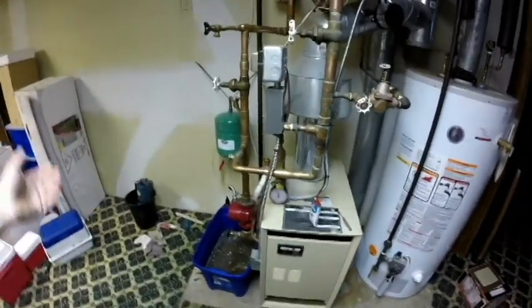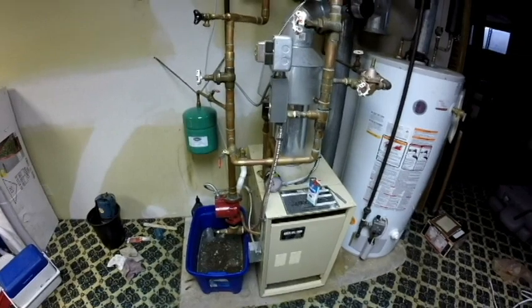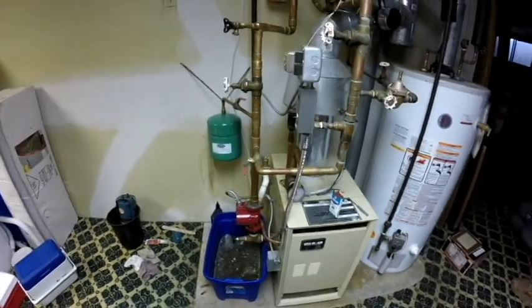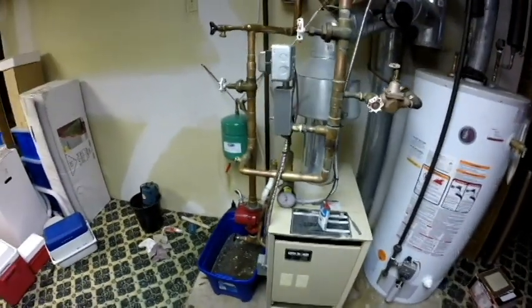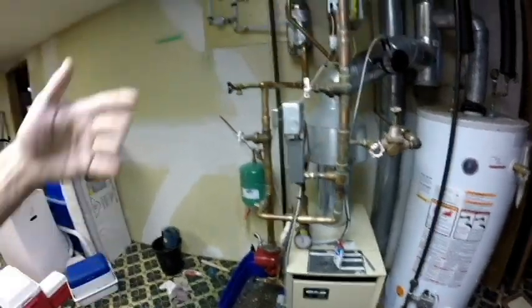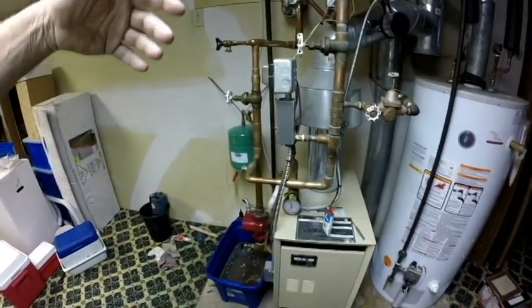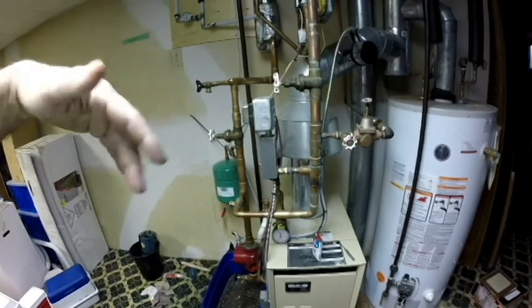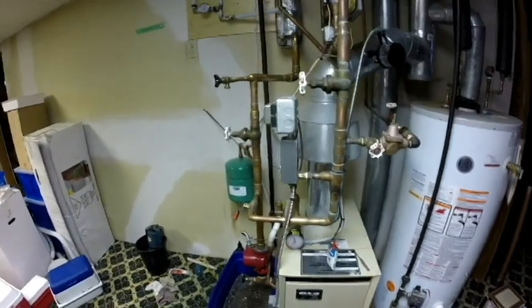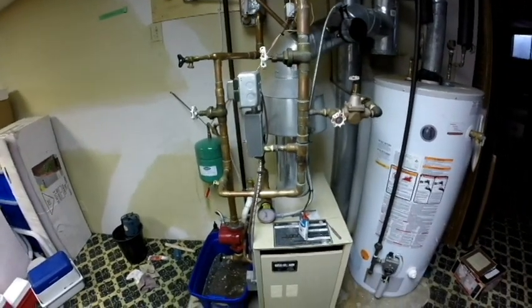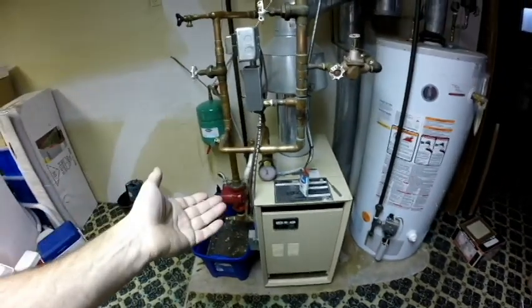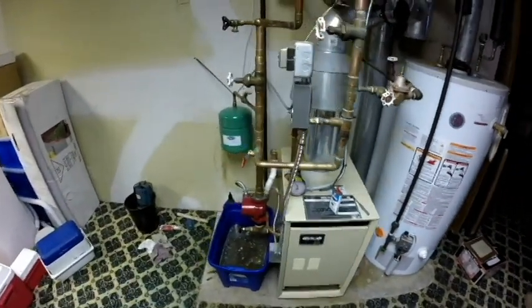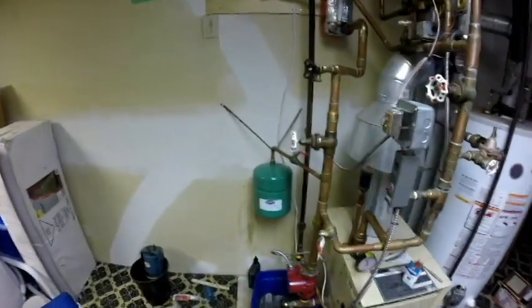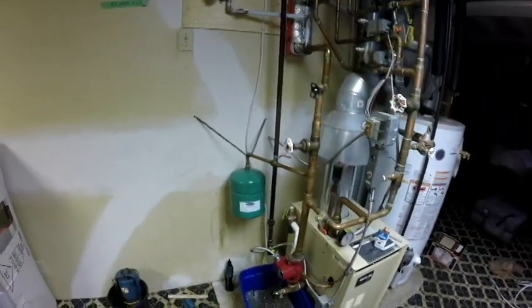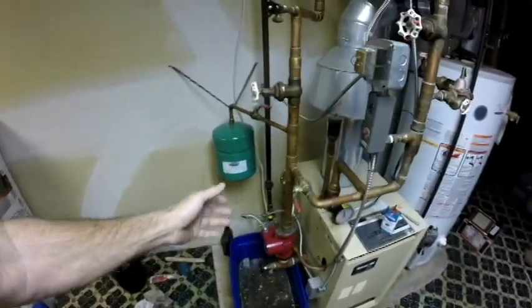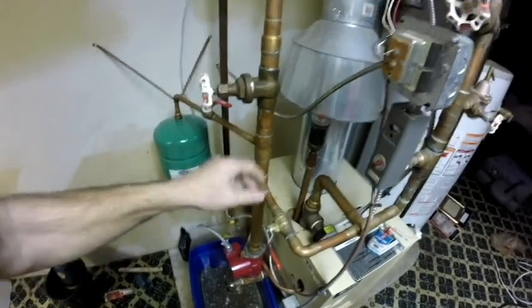That way I'm never without heat, and it keeps the system warm. The other advantage to that is I can easily switch between the two. If I go away or whatever, I just basically shut this thing off and the gas boiler takes over. Anytime I'm home, both systems are up, and now it just shut off. So that means now that there's no longer water flowing through the house system.